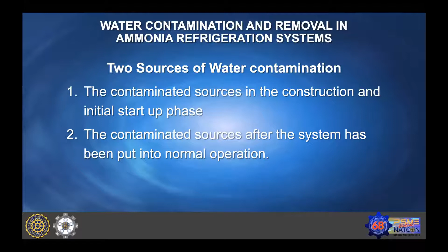So when construction is going on, at initial startup, in what ways does water enter the ammonia system? It may happen that many vendors, many pressure vessel manufacturers, do hydro pressure testing. We recommend dry nitrogen testing, but many people do hydro testing. When hydro testing is done, water remains in the vessel, not properly cleaned or evacuated. That water will remain in the system continuously.